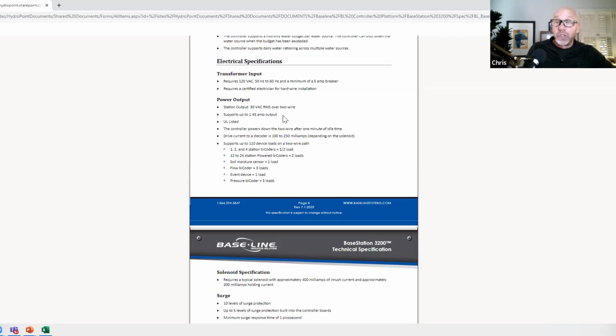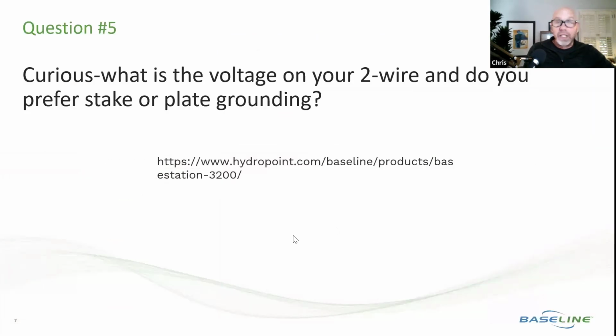And in regards to stake or plate grounding, which do we prefer? The answer is, depending on the site and location, are we able to use a ground rod, or do we have to use a plate because of constraints? Either way, or based on preference, we don't care - we just want to make sure that when grounding is done, we're at 25 ohms or less in a resistance test.